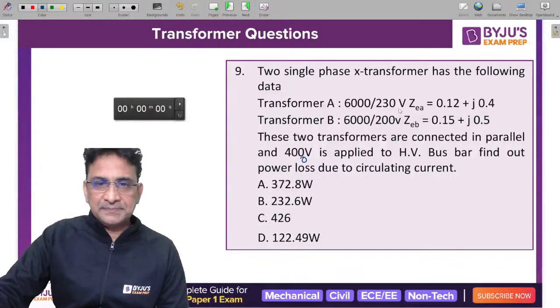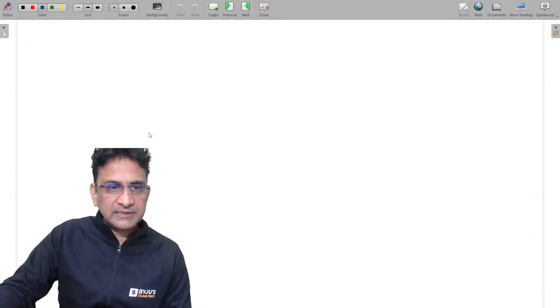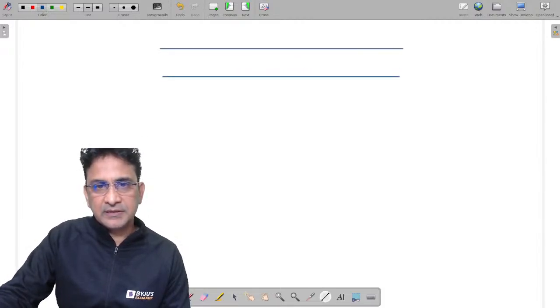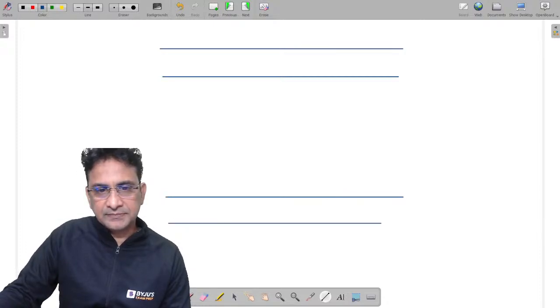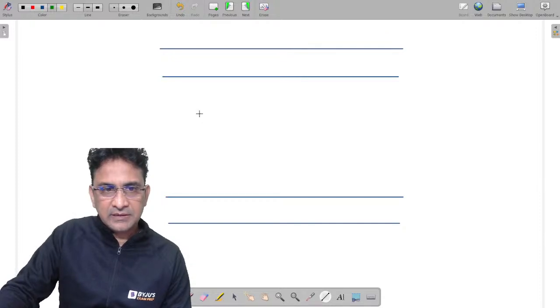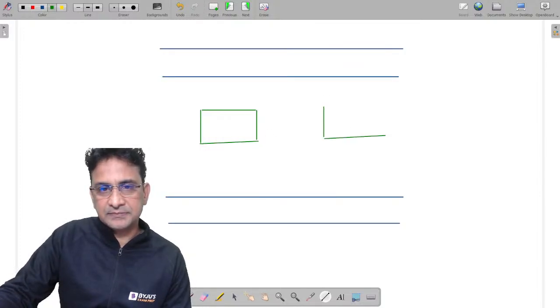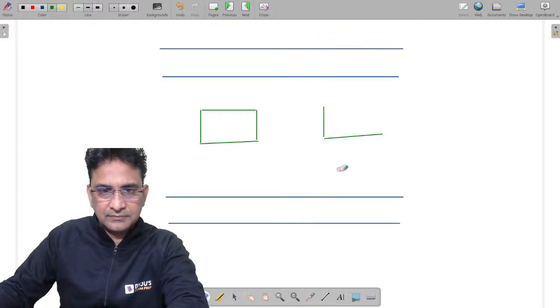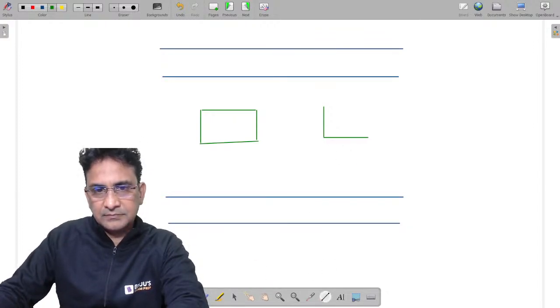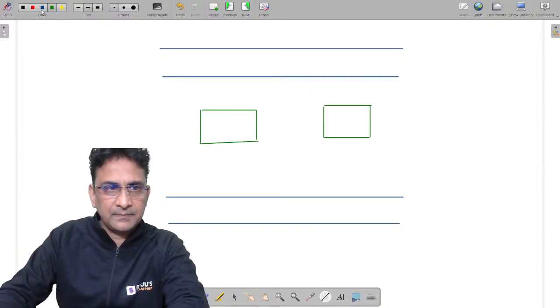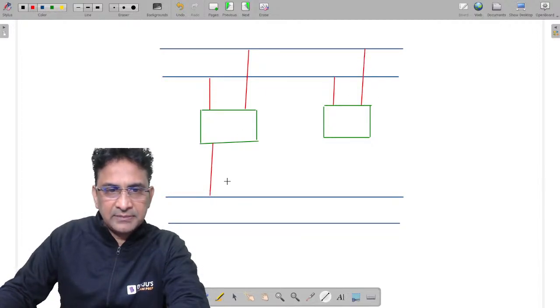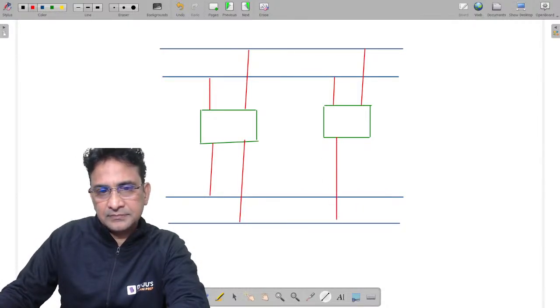122.32. Okay, see, this is my single phase transformer. In the single phase transformer, we have an incoming bus bar and an outgoing bus bar, and between these two bus bars the two transformers are connected in parallel, transformer A and transformer B. Their primary side is connected to the primary bus bar and secondary is connected with the secondary bus bar. Is it clear?